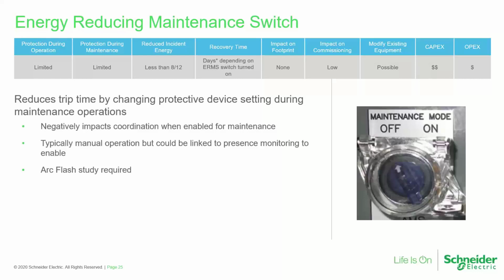Impact on commissioning for this one is fairly low. Maybe you're doing tests with maintenance mode off and maintenance mode on, to make sure the switch is actually doing something, but it doesn't add too much to the complexity. Where we are saying, in our application notes, you may have impacts on coordination when enabled for maintenance.